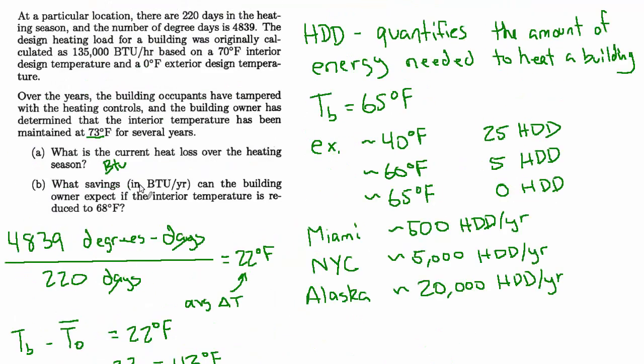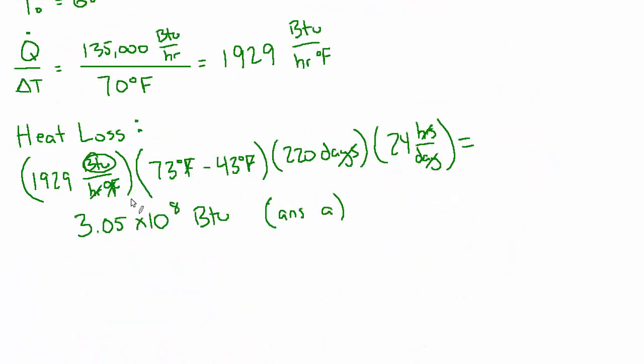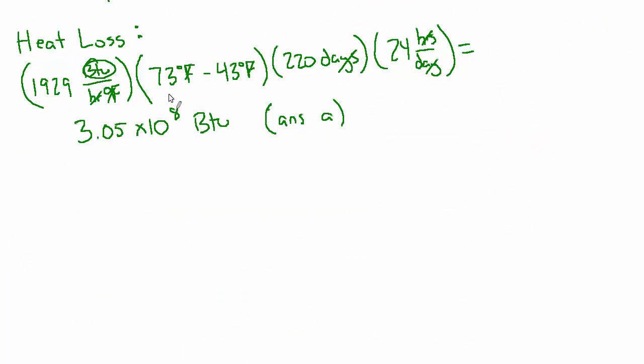Now for part B, they want us to find the savings that the building owner can expect if the interior temperature is reduced to 68. So what would change if we were to reduce that interior temperature? It's really the same calculation, except that instead of the interior temperature being 73, it's going to be 68. So the delta T, rather than being 30, is actually going to be only 25. And we could calculate the total amount of energy using a delta T of 25, and then subtract from answer A, and we would have the difference. Or if we want to go directly after the savings, we can run this same calculation with a delta T of 5, and it'll work out just the same. So let's do that. It's a little more direct.